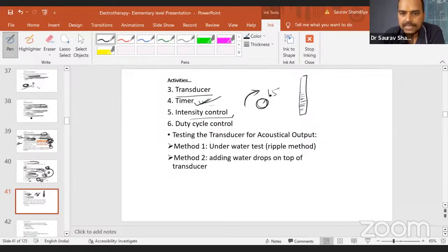So what happens is, when you increase the intensity, 0 to 1.5 or 2.5 or whatever, the light also grows here. I mean, you see the LED, more lights start lighting here. So what is the benefit of this? The benefit is, suppose your intensity is not working, okay, your light only will not move up, no matter how much you are moving your knob, whether because of mechanical breakage or whatever be the reason. Your knob is moving but light is not going up. That means the intensity is a trouble. If sometimes light is going up and knob is not moving, of course physical damage.